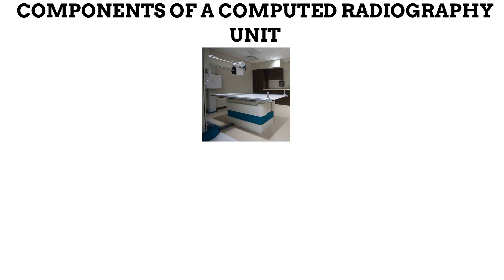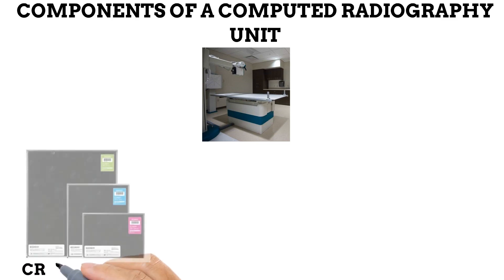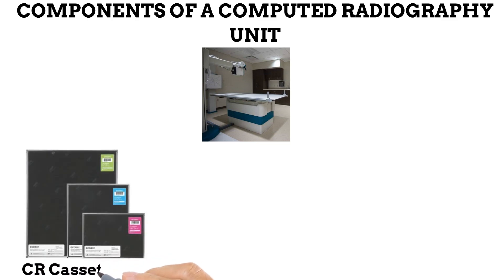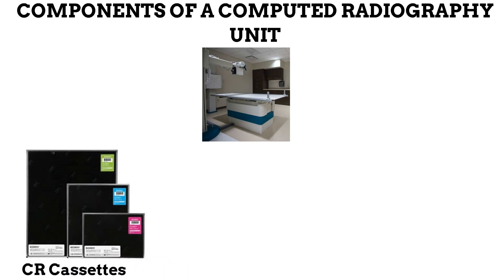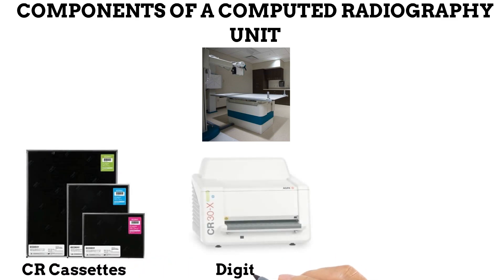Now that we've found out the similarities between a computed radiography unit and a film screen unit, let us look at some equipment you'll find only in computed radiography. These equipment are the special computed radiography cassettes, a digitizer, and a computer with special operating and system software.